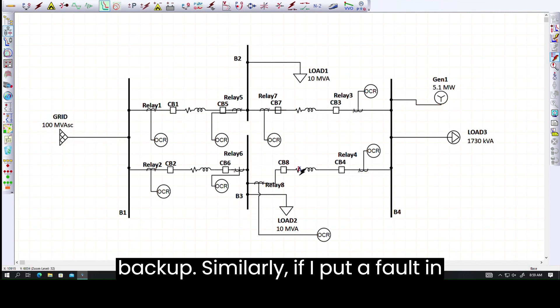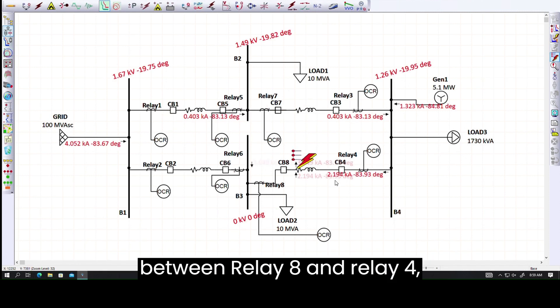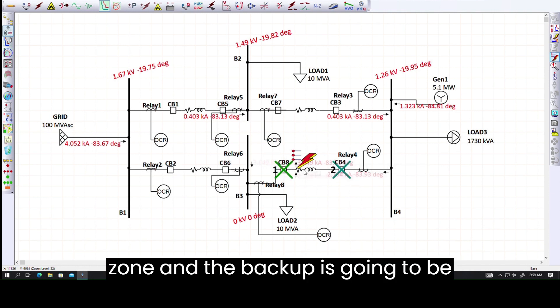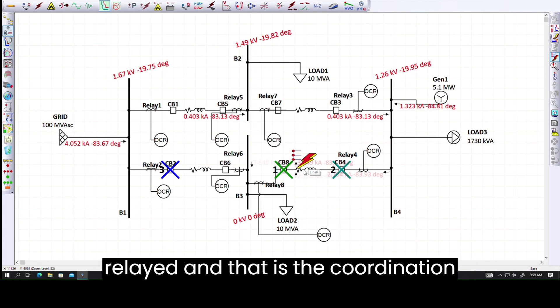Similarly, if I put a fault in between relay 8 and relay 4, relay 8 is going to be the first to trip, and relay 4, isolating the fault in this zone. And the backup is going to be relay 2.